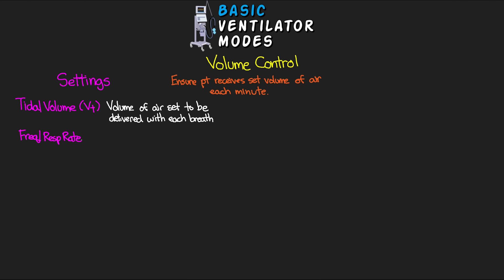The next setting is frequency, also known as respiratory rate, abbreviated as F or RR. It's how many breaths per minute are being delivered to our patient. The way this triggers is the vent takes the respiratory rate you set, divides it into 60 to figure out the amount of time between each breath, and when that amount of time has elapsed it triggers another breath to be given.